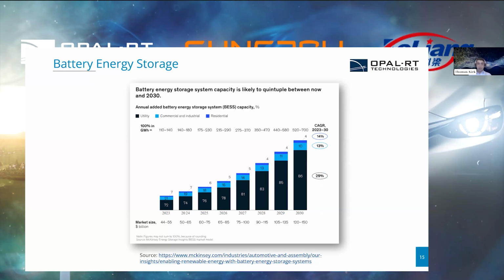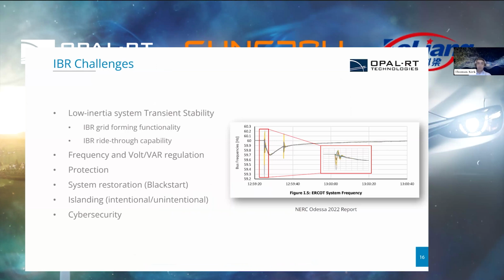So this has a lot of challenges associated to it. What are those challenges? On the right there's a graph, this is from NERC, a US reliability organization, and what you're seeing here is the impact of an event on the grid where solar generation is disconnected. In the context of this event, it wasn't even a grid that was weak, there was substantial inertia in that grid, and it still had this substantial impact on the frequency. So every year there's more and more reports of events such as this, and we're seeing that with the increase in those resources, it's only going to have more and more impacts.